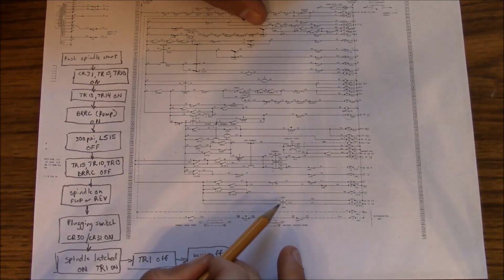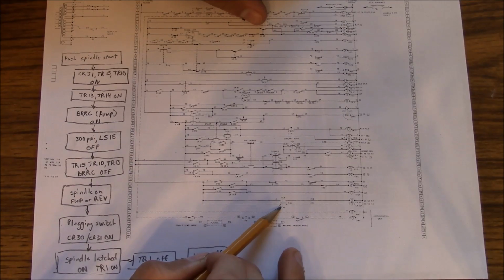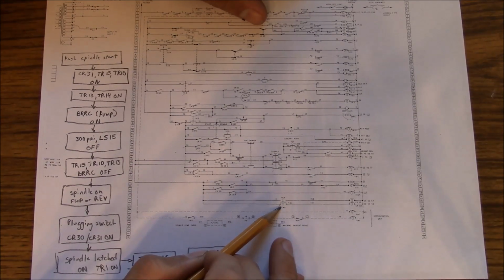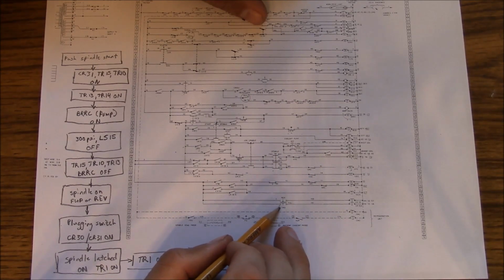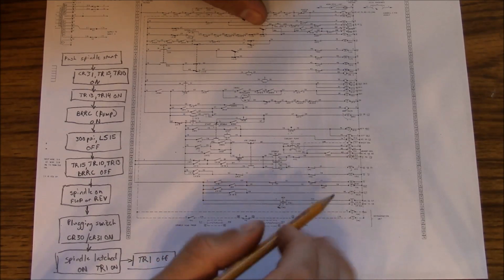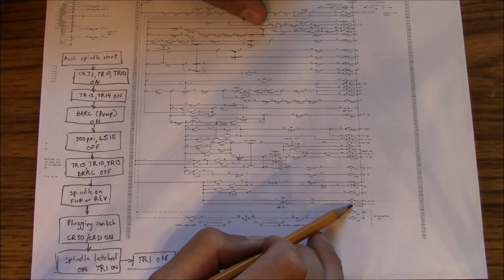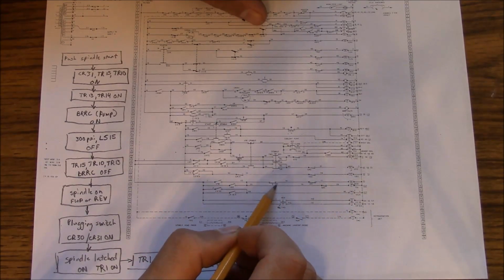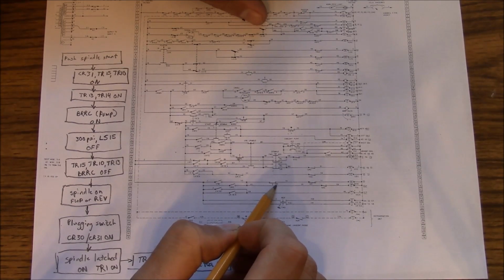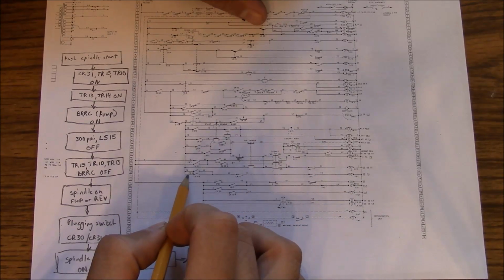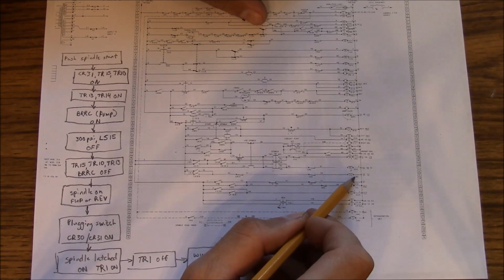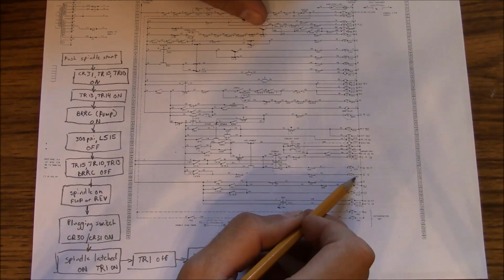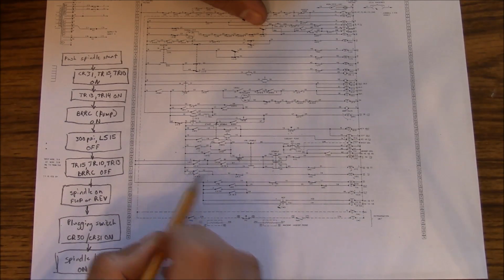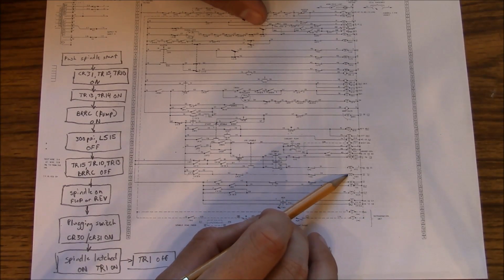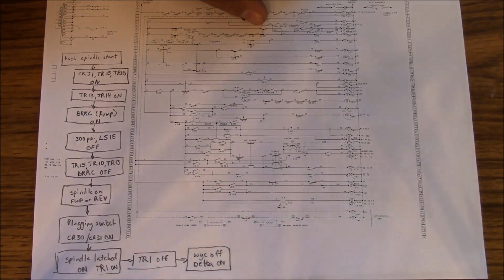So once the motor starts turning, this down here is what's called a plugging switch. The plugging switch basically turns itself on anytime that it senses rotation of the motor. You can think of it kind of like a centrifugal switch. So anytime the motor is running and this plugging switch is active, it's going to turn on either CR30 or CR30A. And the next step, once this timer relay TR1 hits its limit, it's going to open up, and then the motor is going to actually shift into SDC, which is the delta coil, and the delta coil requires CR30 or 30A to have power. So you need the plugging switch to be on before the motor switches to its delta setting, and then once the motor switches over to delta, it'll continue to run until you hit the stop button.